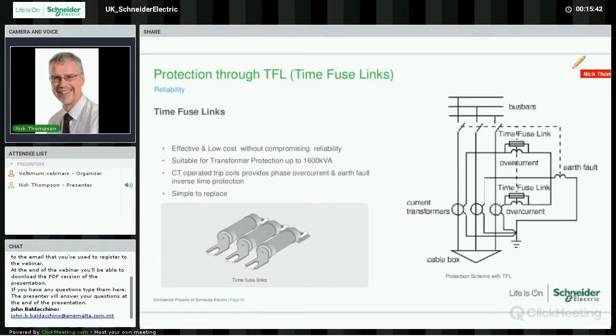The most popular form of protection, and it is the simplest, is time fuse link. The principle being that the two fuses provide overcurrent protection: if the secondary current from the CTs exceeds the fuse rating, then the trip coil will operate. Unfortunately, you can only go up to a 1.6 MVA transformer using this form of protection, but it is by far the most popular form of protection that we use here in the UK.